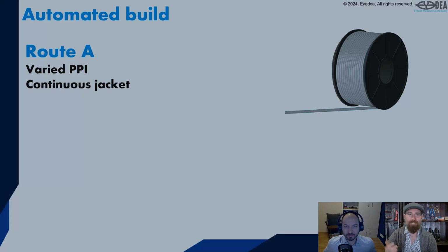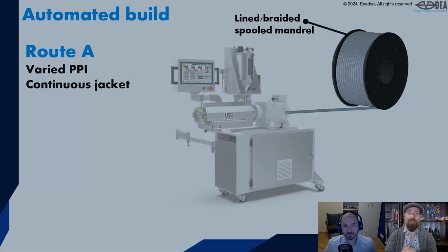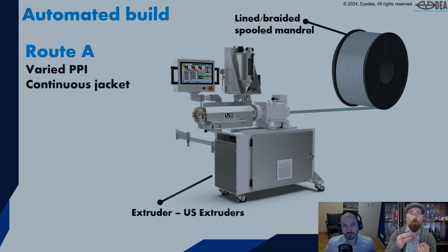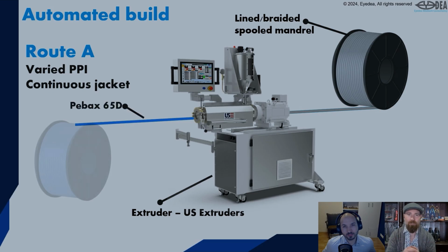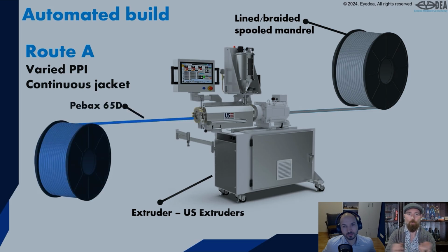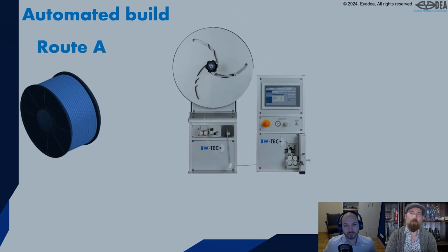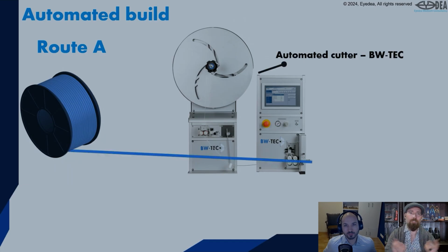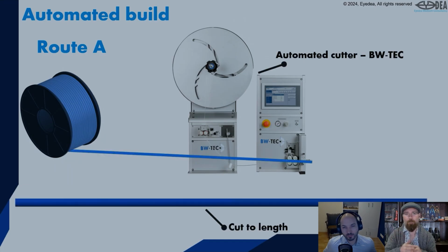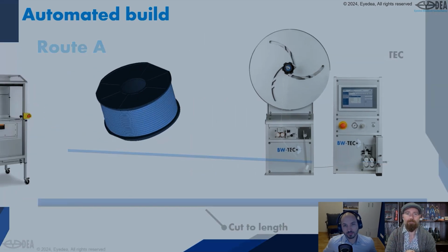One path you could do is just continuous braiding that goes straight into an extruder, and you do what's called a co-extrusion. So this is just placing a layer down on the outside. This is if we all wanted the same material. So say we wanted PEBAX 65D the whole way throughout, and then we get our spool of PEBAX 65D with the braid, with the liner, and everything else included. If you wanted to then cut this to length, you put it through an automated cutter. It'll slice it to length. You have sections now of your catheter shaft. You do have issues with those wires potentially open at the end, but there are fixes around that.